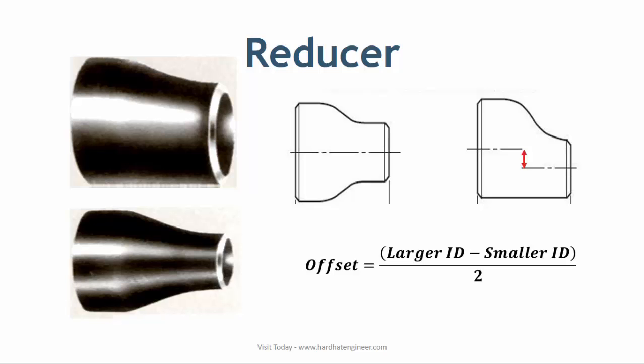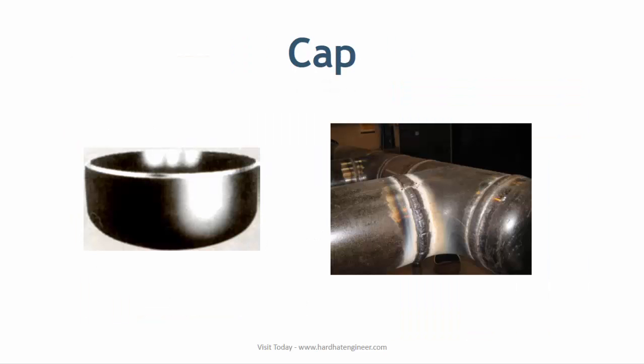Pipe caps are used at the dead end of the piping system. By welding a pipe cap, you can eliminate any chance of leakage during operation. It is cheaper and safer compared to a flange joint if there is no immediate need for a future connection. However, dead ends are susceptible to corrosion, so you have to check the thickness at regular intervals.